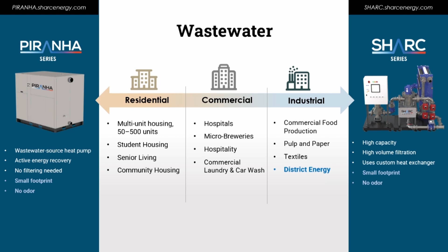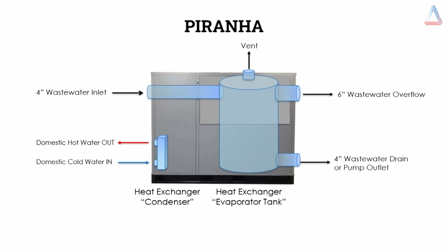And then we just extract the energy using a refrigerant sheath that's around the tank to then push it through a typical refrigerant compressor loop to get more heat, and we can push up to 140-degree potable hot water out of this box. And this is what a typical above-grade piranha looks like.